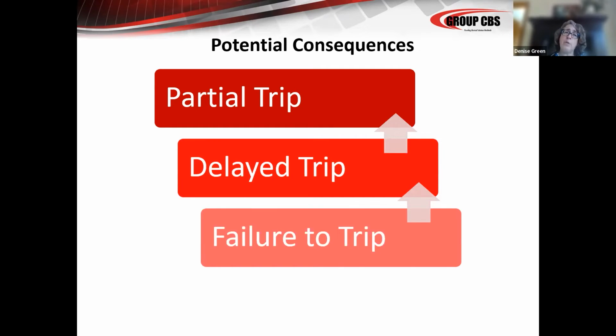So if you maintain breakers and you check your interrupters and you make sure that the integrity is good, either with the standard methods of using a high potential test set to do vacuum integrity, or if you use the MAC test set to get a more quantitative value on your vacuum interrupters, that gets you a long way toward avoiding a complete meltdown of your breaker, because under fault, it will not interrupt. So did that answer your question?